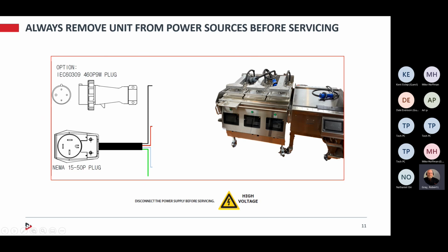Take a look at your connections, your plug-ins. You have 2 different kinds. You have the Mennekes or the pin and sleeve. This is for the installations that are going to be like an island type install or the middle of the floor where the electrical power comes down from the ceiling, not inside of a wall. And then the NEMA configurations are units that are installed against the wall like you saw in the picture before.